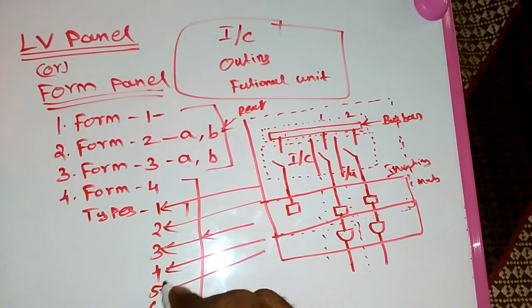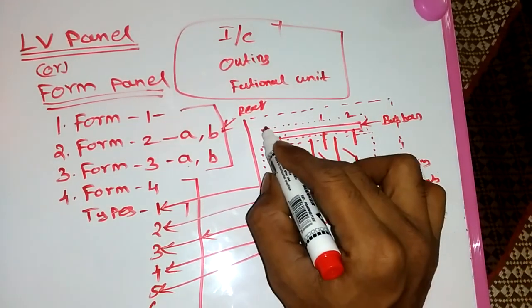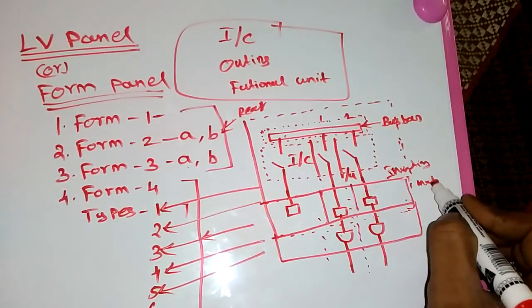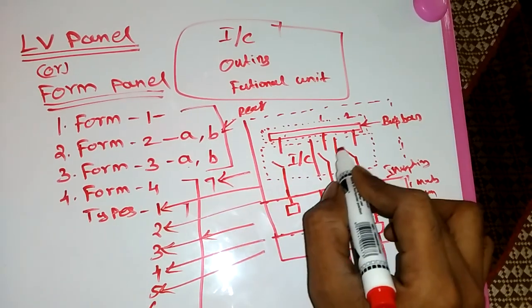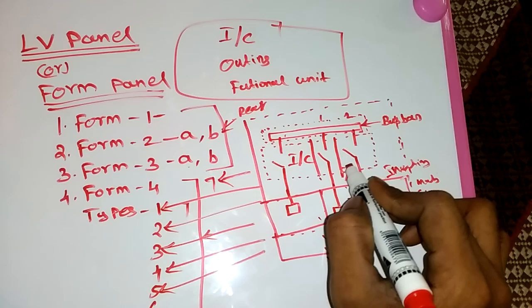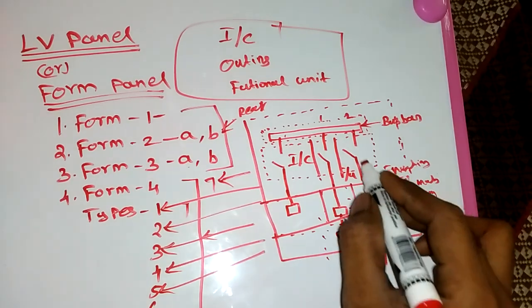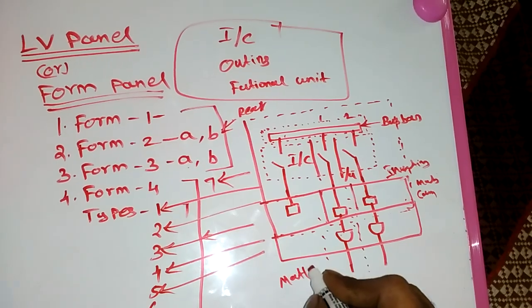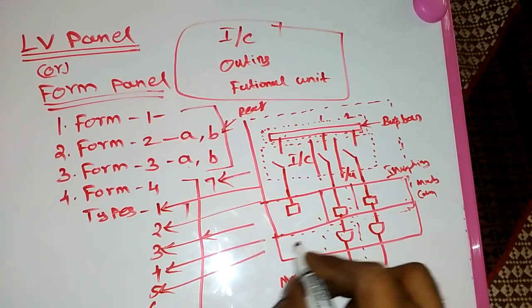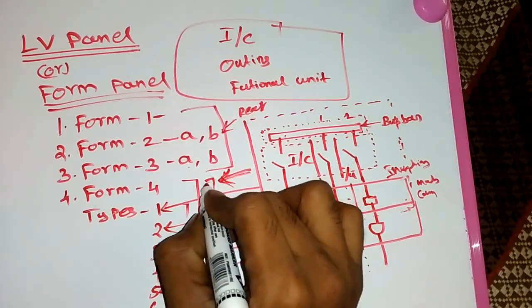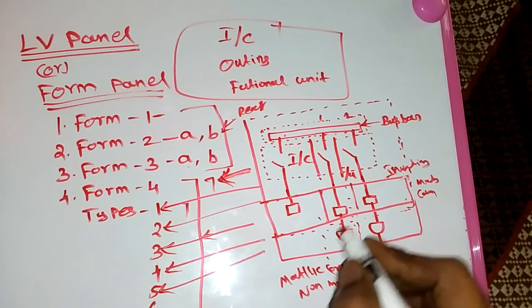In Type 5, we separate only the external terminals using non-metallic material, and the bus bar is separated by insulating cover. In Type 7, the total compartment is completely separated — that means incoming isolator, outgoing functional unit, outgoing external terminals, and glands — all terminals are separated by metallic or non-metallic material. Form 4 Type 7 is the most current standard and is used for very large projects needing more than 60 to 70 outgoings.